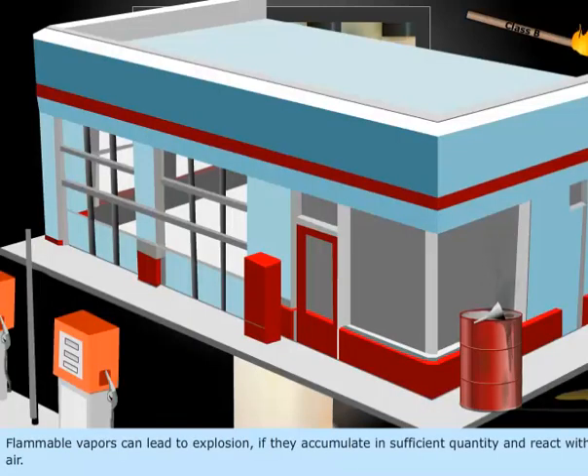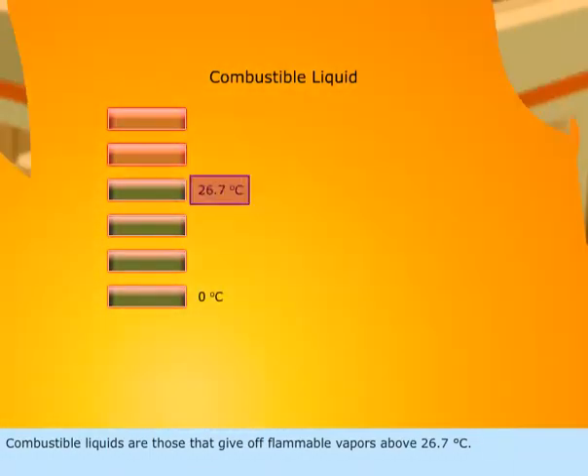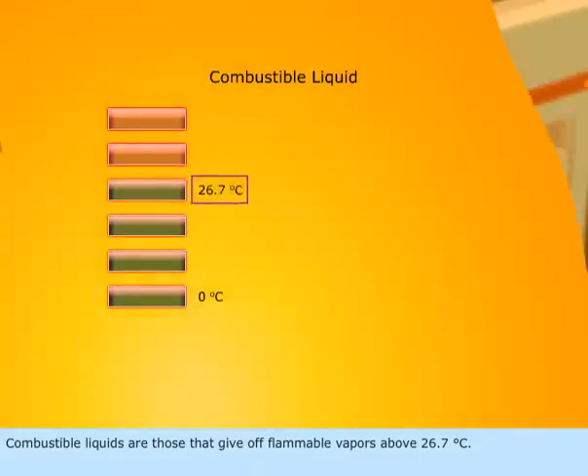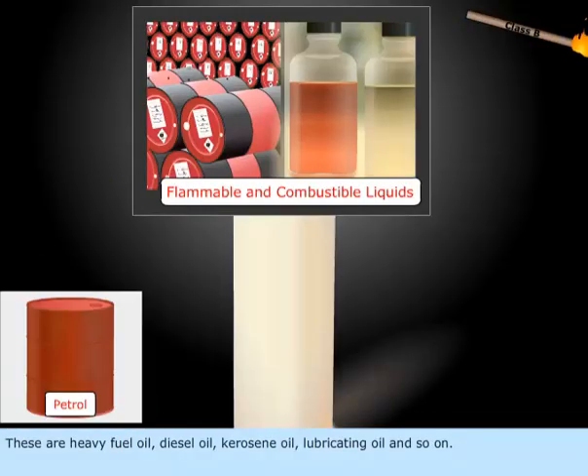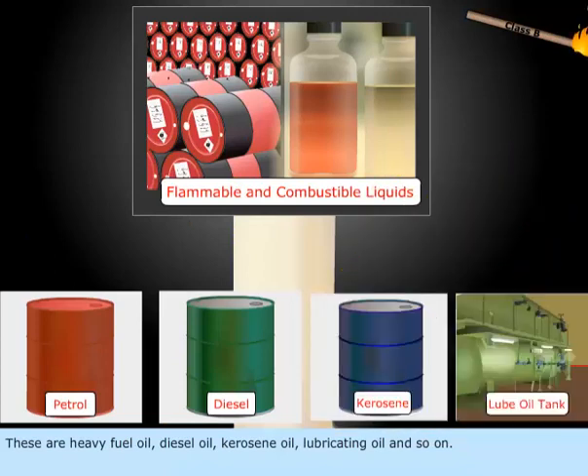Flammable vapors can lead to explosion if they accumulate in sufficient quantity and react with air. Combustible liquids are those that give off flammable vapors above 26.7 degrees Celsius. These are heavy fuel oil, diesel oil, kerosene oil, lubricating oil, and so on.